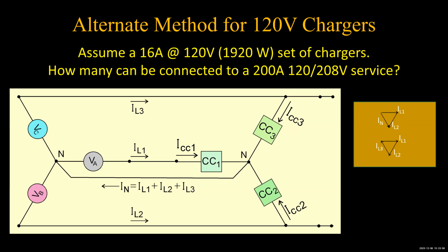Now, third harmonic, normally what that's going to do is give you some neutral current, but not necessarily change your line current. And it's the line current that's going to trip the breaker. And the neutral is not going to be a reduced size anyway on this. It's going to be full size. So given that third harmonic, what it does is when the three add up in the neutral, then you have something different from 0. But it never exceeds the value of any of the single line currents. So I guess even if there is a little bit of third harmonic, it's not going to be an issue.